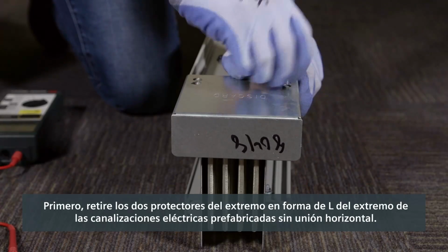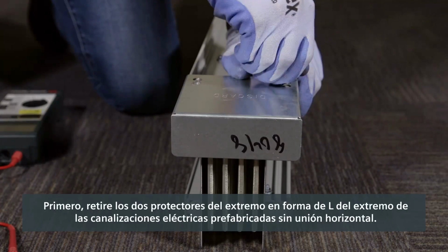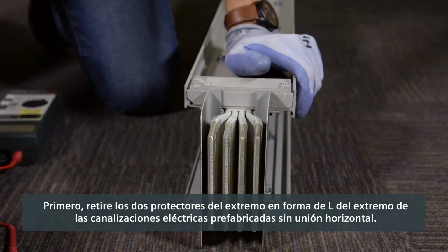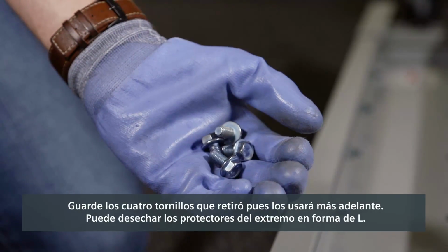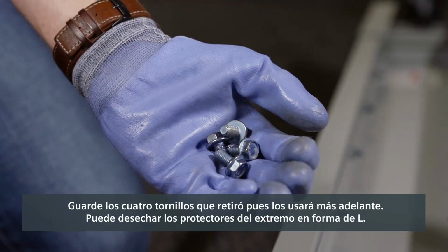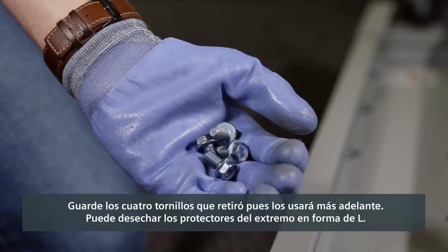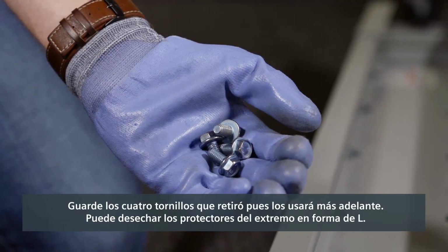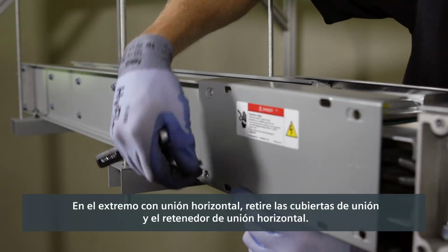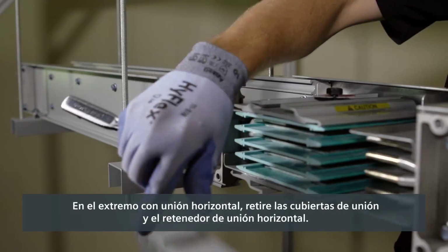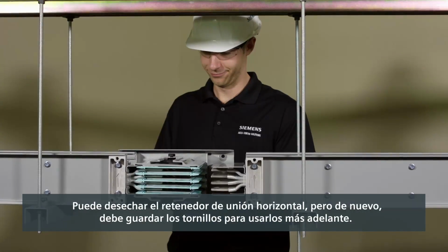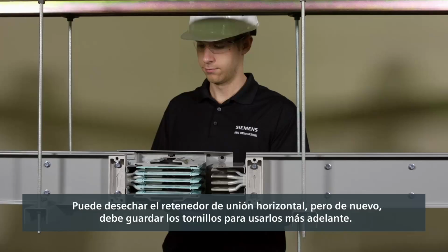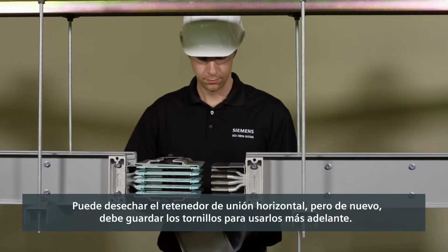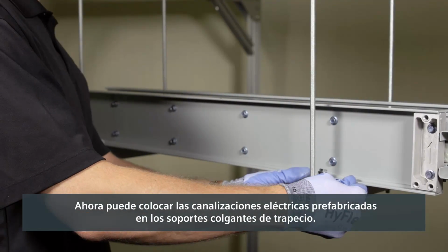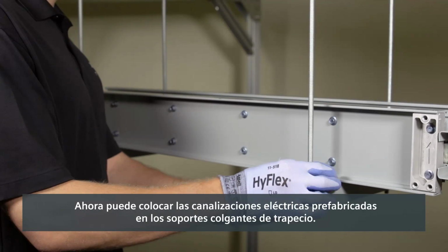First, remove the two L-shaped end protectors from the end of the busway without a joint stack. Keep the 4 screws you remove because they'll be used later. The L-shaped end protectors can be discarded. On the end with a joint stack, remove the joint covers and the joint stack retainer. You can discard the joint stack retainer, but again, retain the screws for later. The busway can now be positioned on the trapeze hangers.